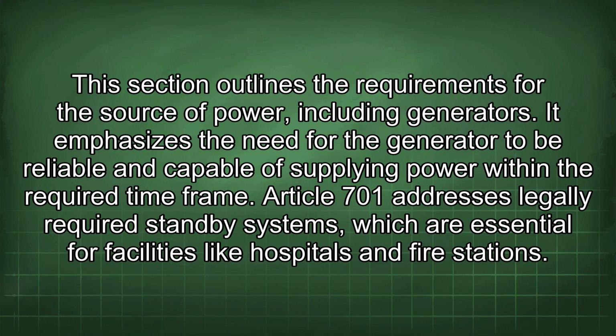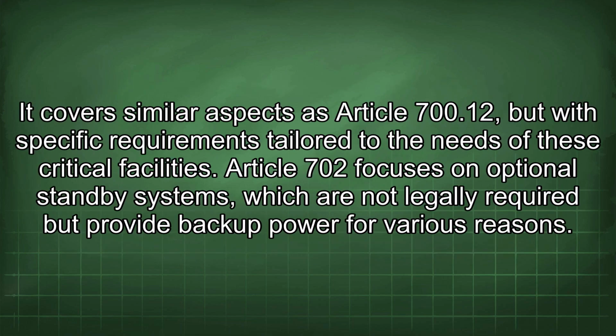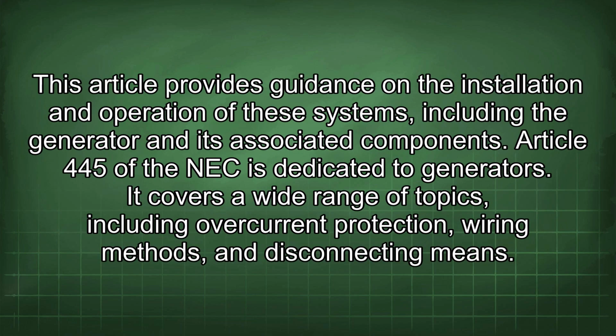Article 701 addresses legally required standby systems, which are essential for facilities like hospitals and fire stations. It covers similar aspects as Article 700.12, but with specific requirements tailored to the needs of these critical facilities. Article 702 focuses on optional standby systems, which are not legally required but provide backup power for various reasons. This article provides guidance on the installation and operation of these systems, including the generator and its associated components.